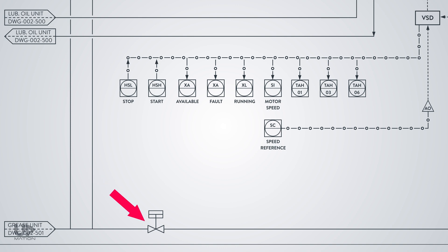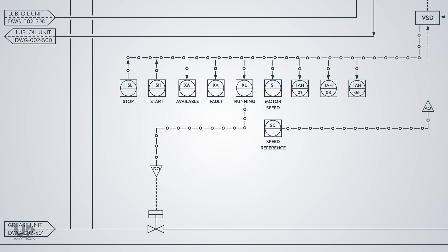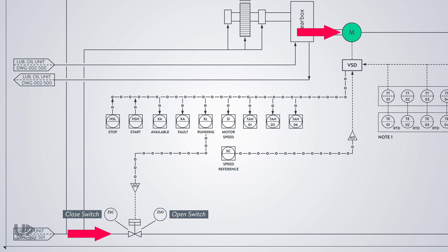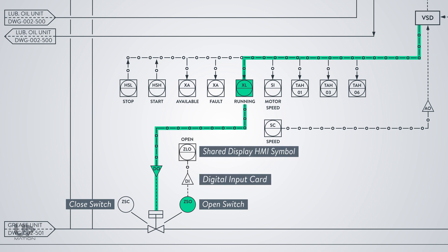Now let's talk about the solenoid valve which opens or closes the grease supply to the bearings of the ball mill. The PLC programmer should write the program to link the opening or closing of this valve to the status of the electric motor, so the PLC logic will open the valve via a digital output card. To know if the valve has executed the open and close commands, it should have open and close switches mounted on its actuator. Upon starting the motor, the grease valve opens and its signal is transferred to the HMI via a PLC digital input card. The same will happen when the motor turns off and the valve closes. I used bubbles for the switches as they are field-mounted.